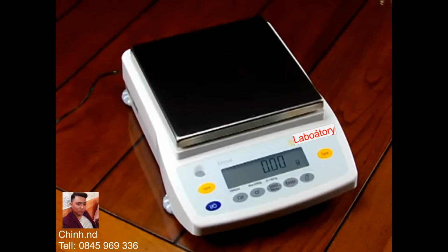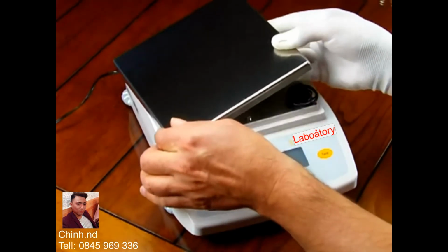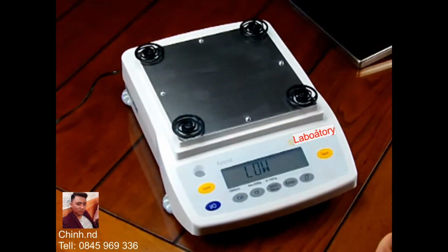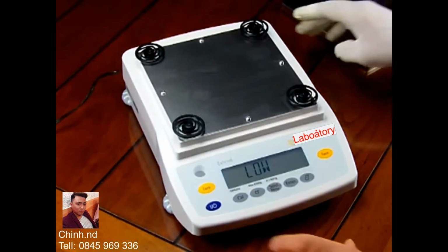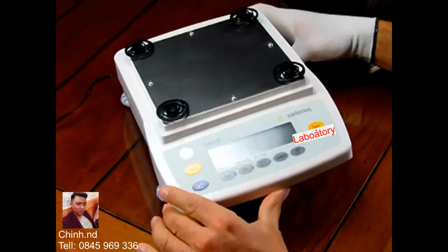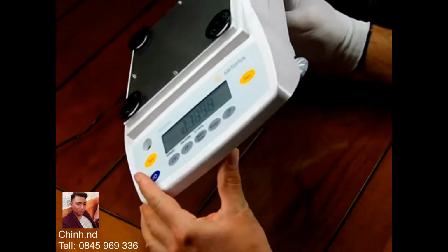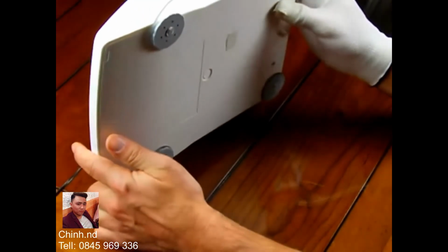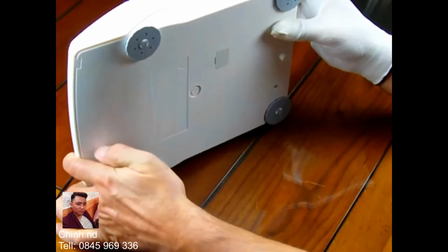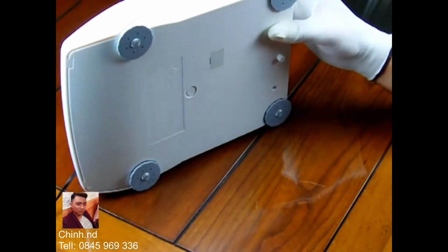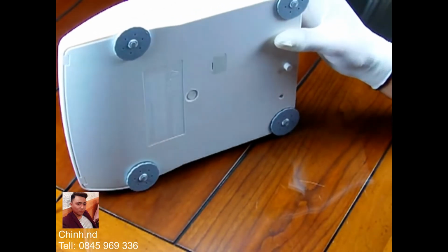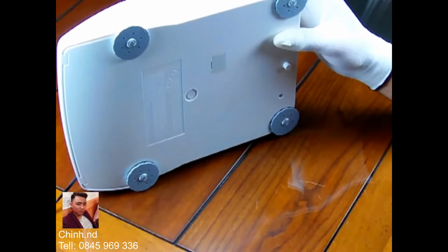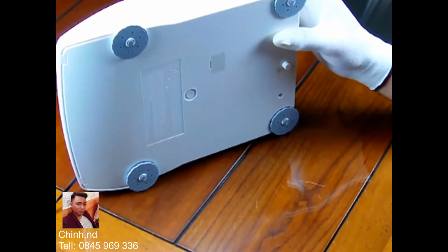The balance also offers 4 adjustable feet. So a lot of other brands on the market, you want to look at this, they only offer 2 adjustable feet, or some balances offer none whatsoever. So the bottom of the balance here, you'll see there's 4 adjustable feet for leveling the balance. And this is critical. When you weigh, your balance has to be level.